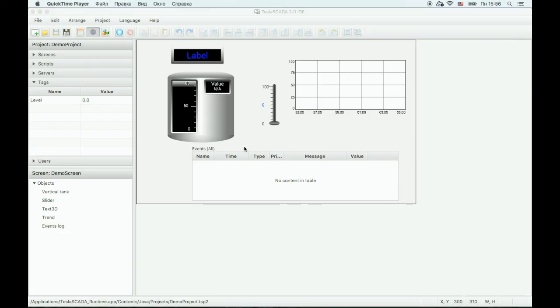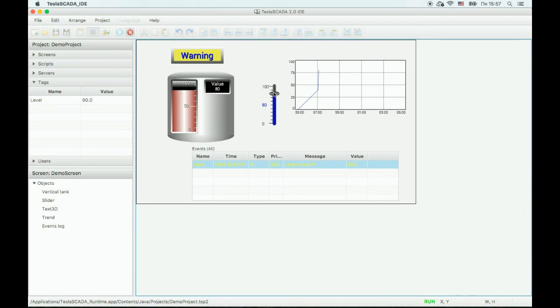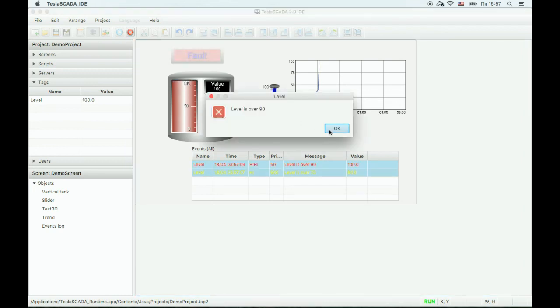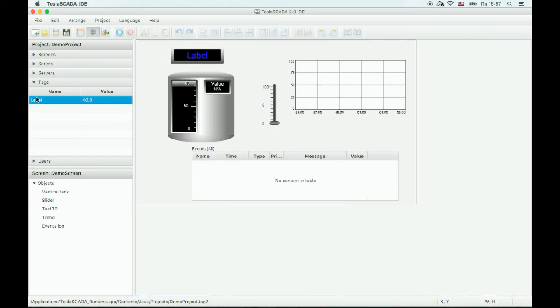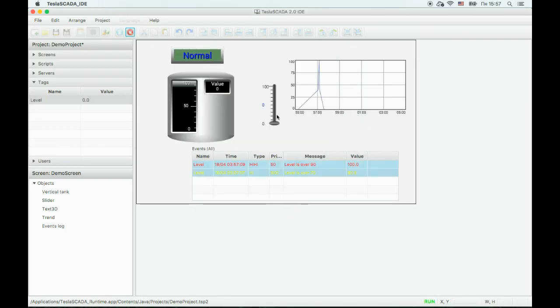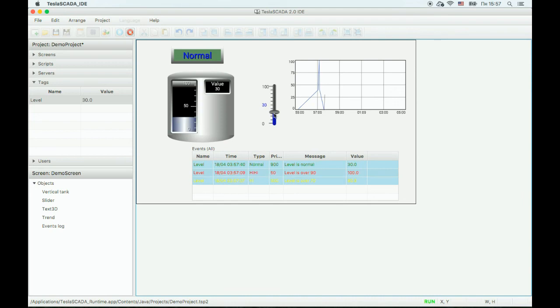Now let's simulate our project. To do this, click the Run Simulation button on the toolbar. For some reason, the alarm message isn't appearing in the event log. Let's check. We forgot to enable the alarm for the tag. Let's start again. OK, now the message appears.